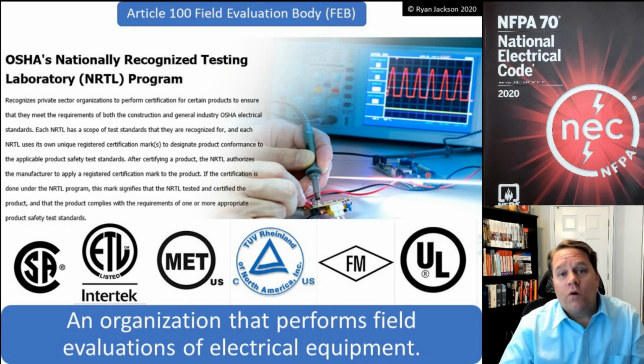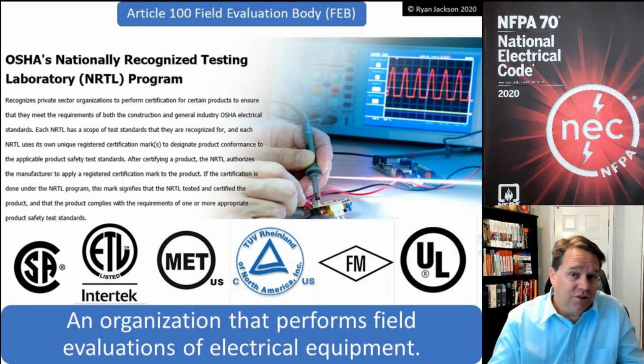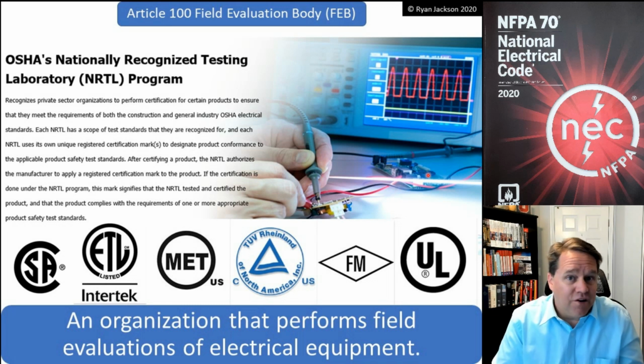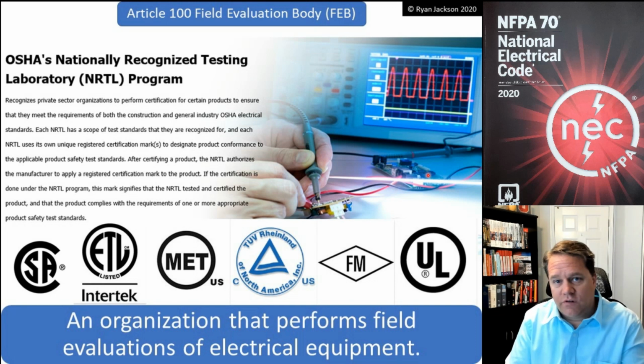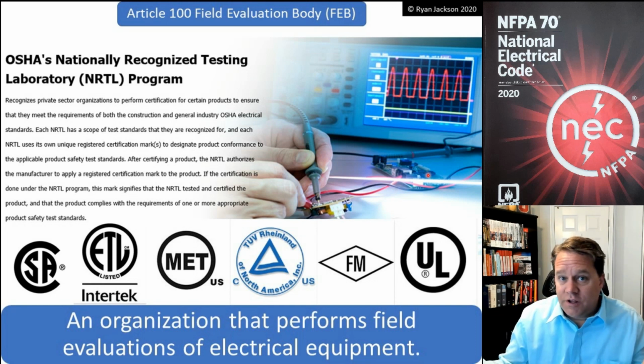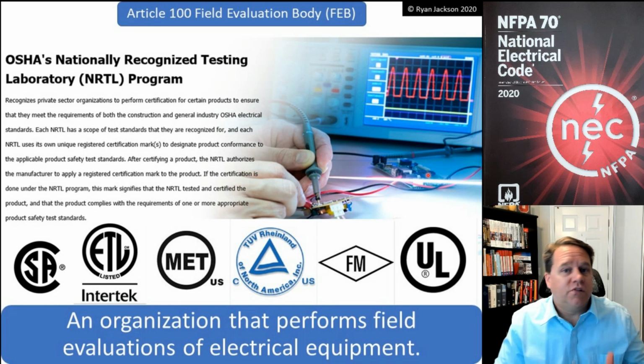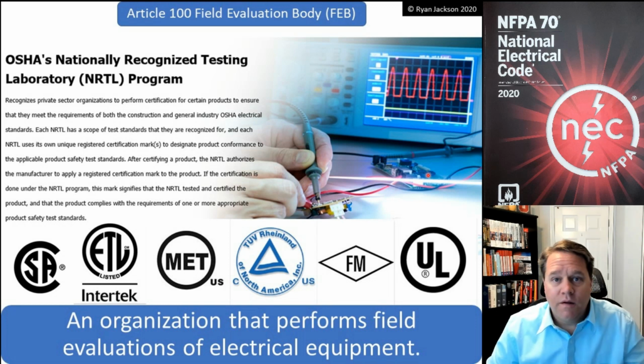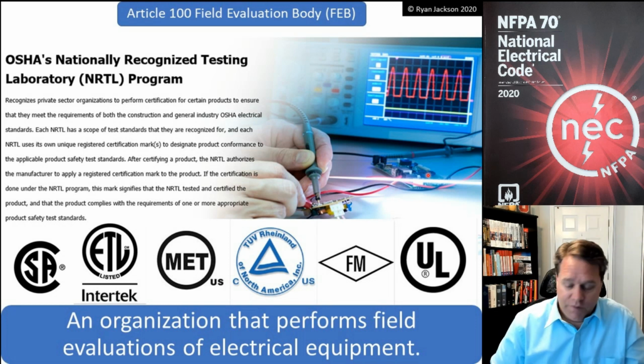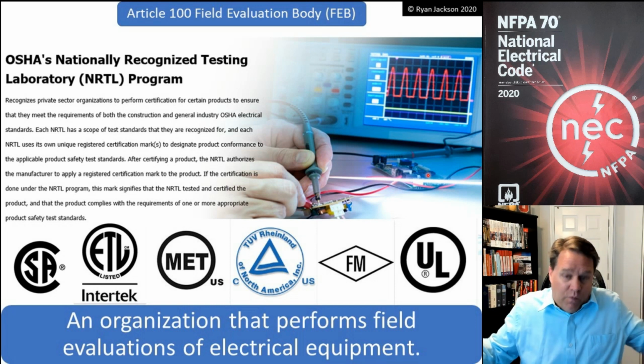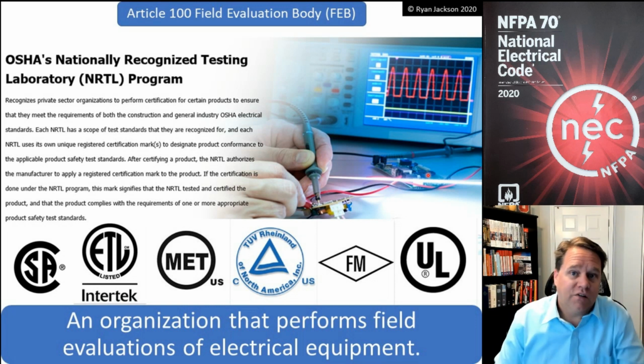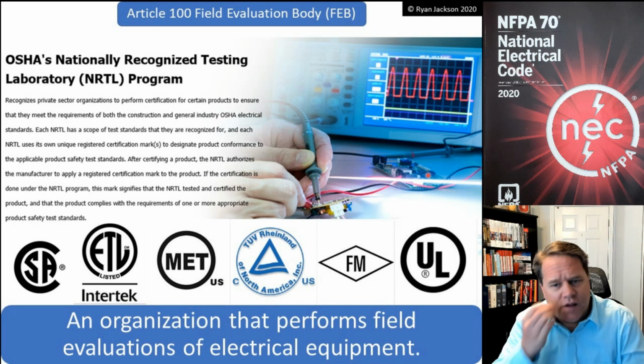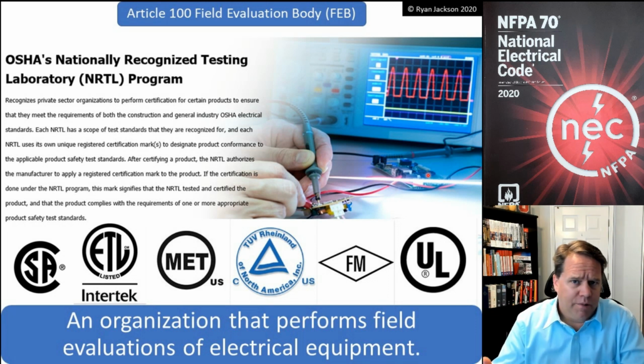There are other products that can't be listed because there's not a product standard yet. When energy storage systems first came out, it took a little while to develop a standard. Before that standard was developed, you couldn't possibly list it. If you manufactured an energy storage system and sent it off to Intertek or somebody and said, test this and list it, they'd send it back and say, what test do you want me to run on it? There's no product standard. So if there's no product standard, then the product might not be listed.